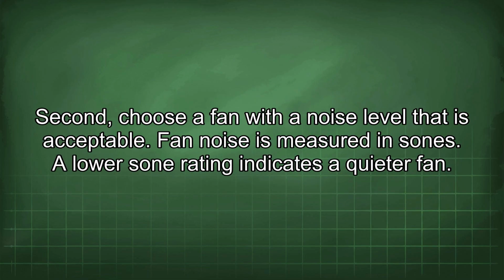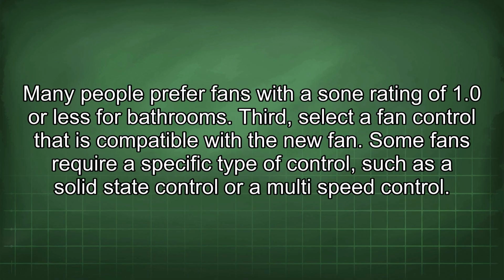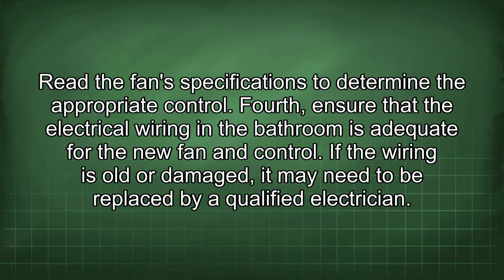Second, choose a fan with a noise level that is acceptable. Fan noise is measured in sones. A lower sone rating indicates a quieter fan. Many people prefer fans with a sone rating of 1.0 or less for bathrooms. Third, select a fan control that is compatible with the new fan. Some fans require a specific type of control, such as a solid-state control or a multi-speed control. Read the fan's specifications to determine the appropriate control.